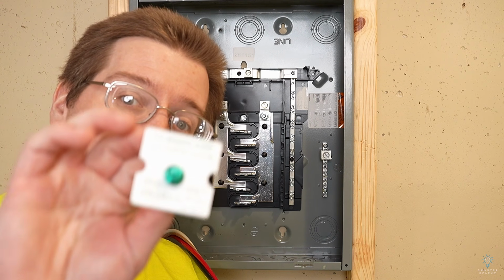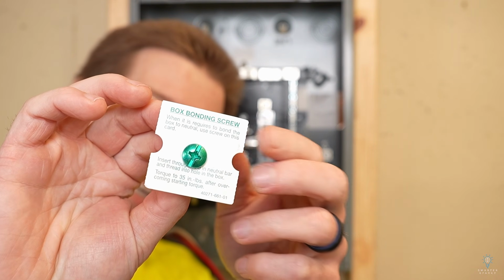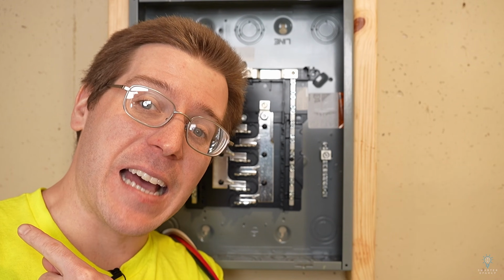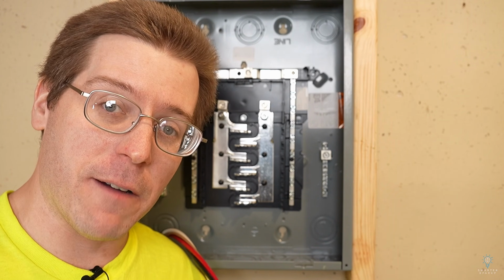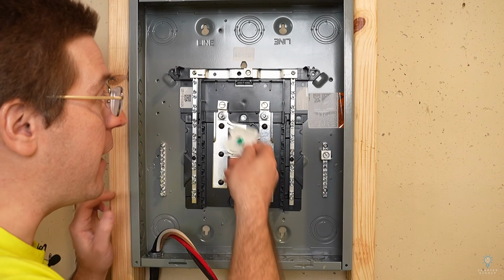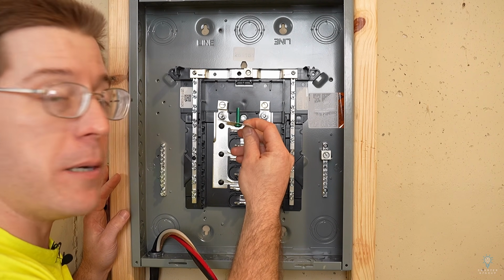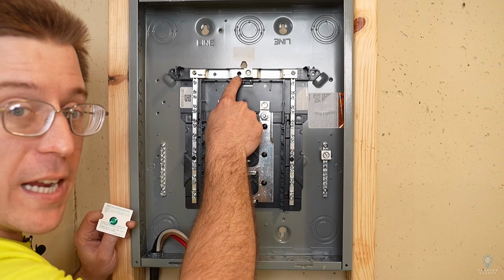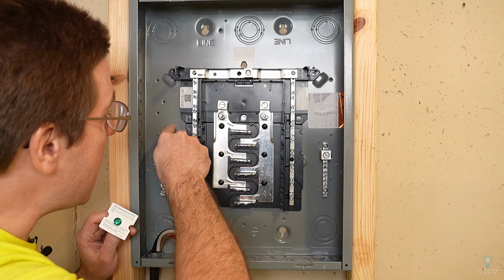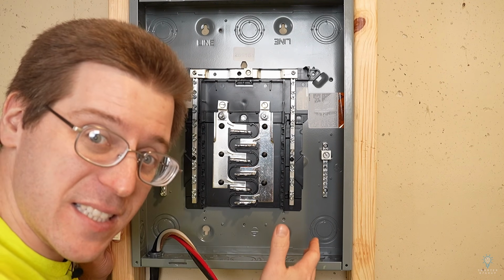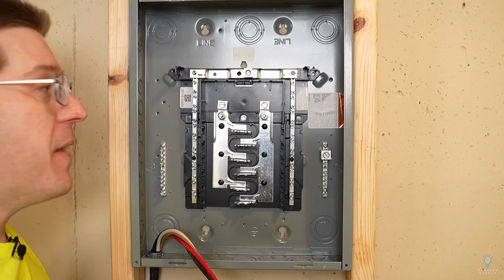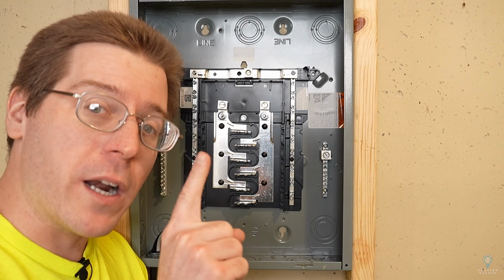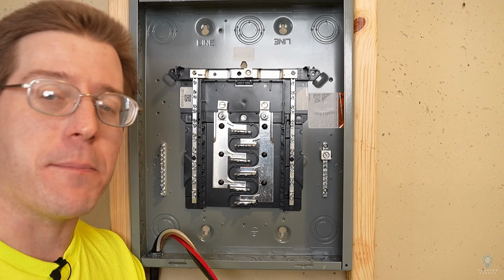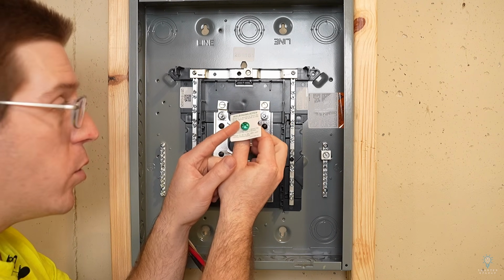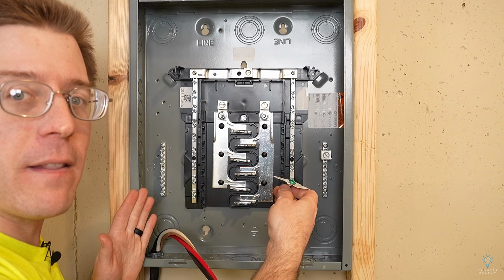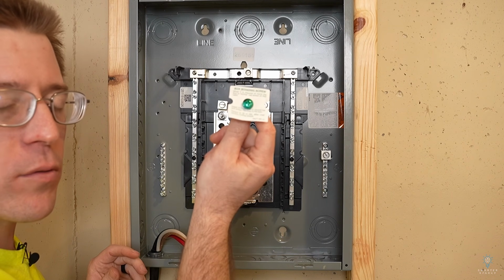That actually brings me to my next point. This panel came with a box bonding screw, and that's the ground screw that I was talking about in the last video that bonds the neutral to the case of the panel. Because we're installing this panel as a sub panel, we do not want to install this green bonding screw. That would actually get installed right here, and it would tie the neutral bar to the actual case of the electrical panel. Because this is a sub panel, we do not want that extra bonding. That's called a main bonding jumper, and you can only have one of those on an electrical installation, and that's always at the main electrical panel. The only time you would use this screw is if we were installing this panel as a main electrical panel. Because this is a sub panel, this screw does not get used.